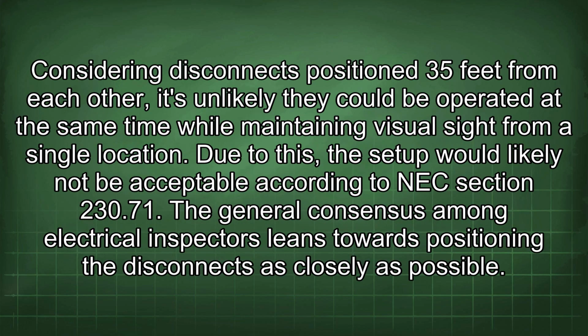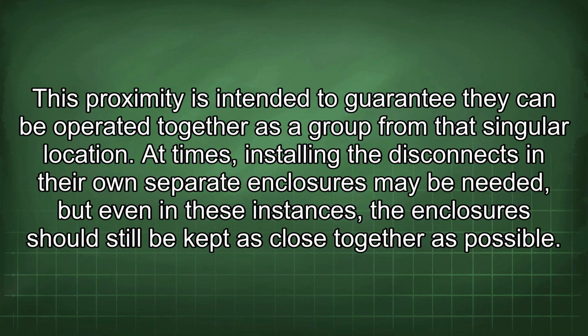Considering disconnects positioned 35 feet from each other, it's unlikely they could be operated at the same time while maintaining visual sight from a single location. Due to this, the setup would likely not be acceptable according to NEC Section 230.71. The general consensus among electrical inspectors leans towards positioning the disconnects as closely as possible. This proximity is intended to guarantee they can be operated together as a group from that singular location.